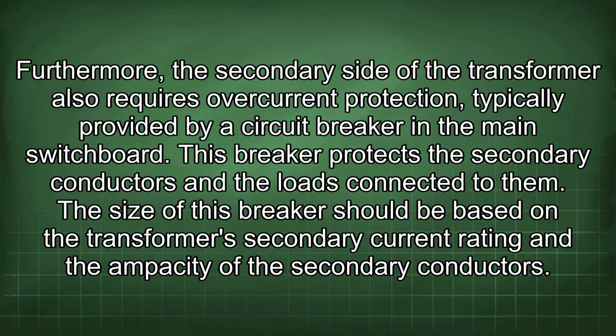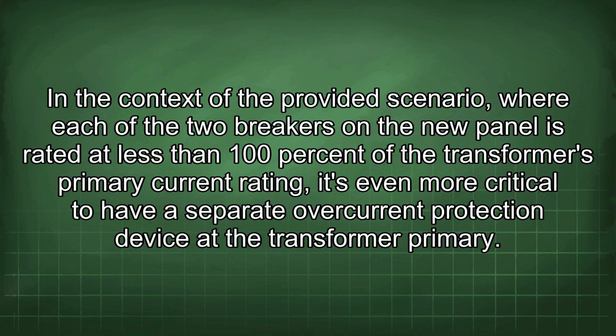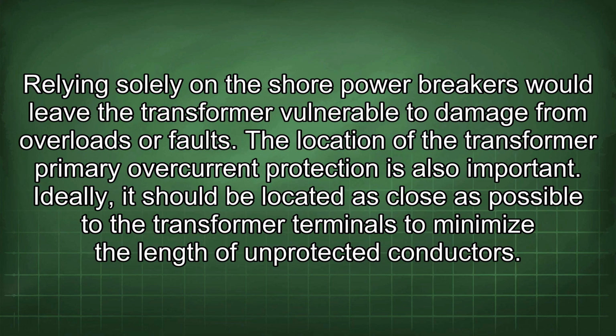The size of this breaker should be based on the transformer's secondary current rating and the ampacity of the secondary conductors. In the context of the provided scenario, where each of the two breakers on the new panel is rated at less than 100% of the transformer's primary current rating, it's even more critical to have a separate overcurrent protection device at the transformer primary. Relying solely on the shore power breakers would leave the transformer vulnerable to damage from overloads or faults.